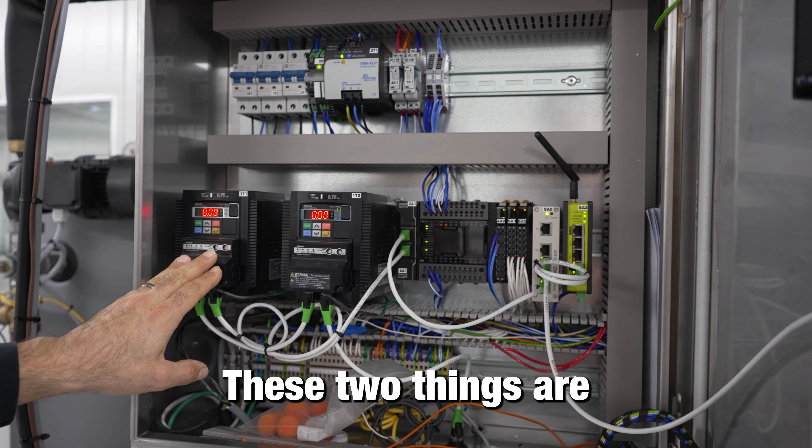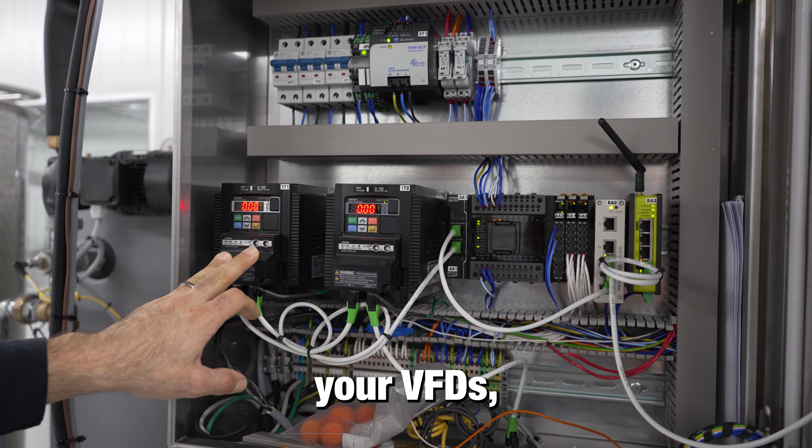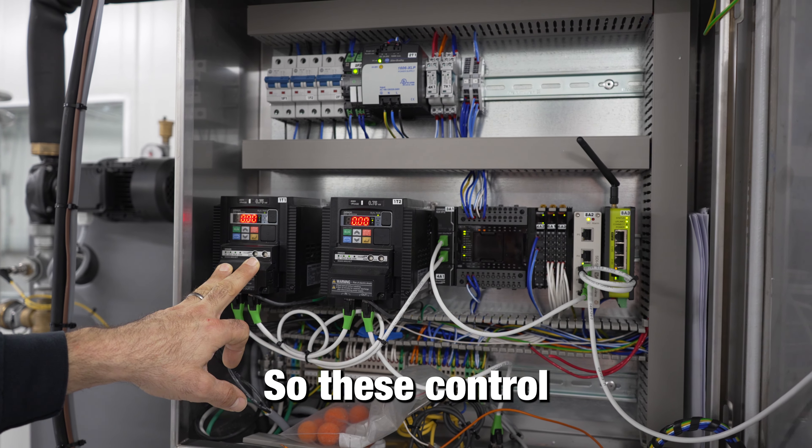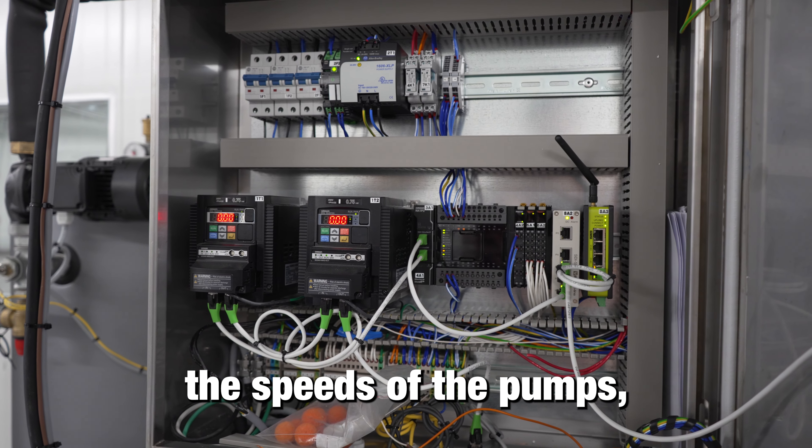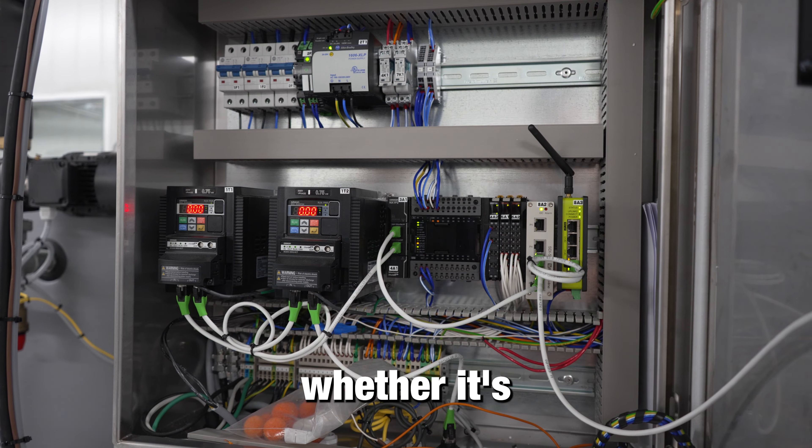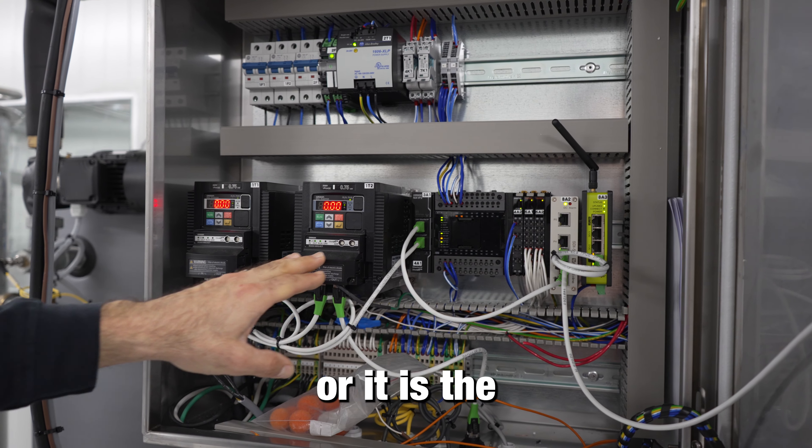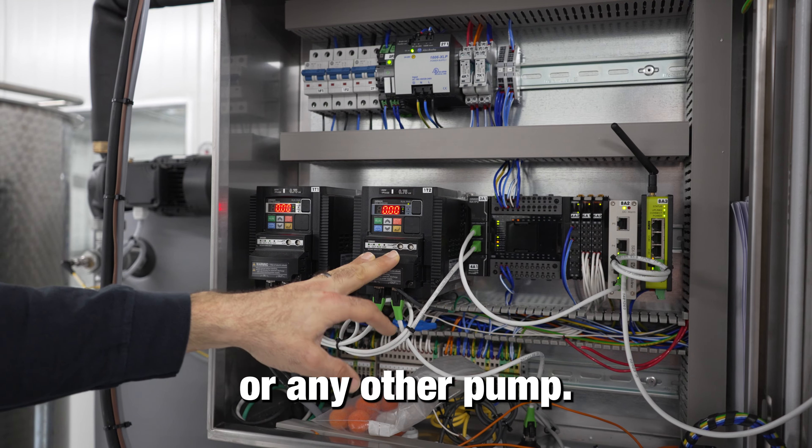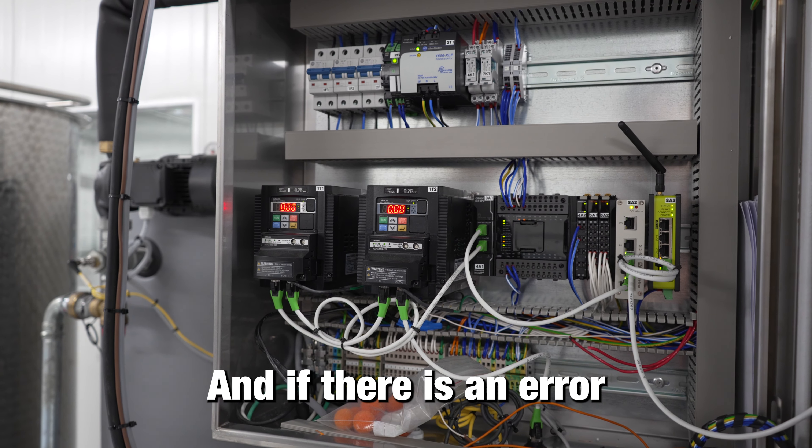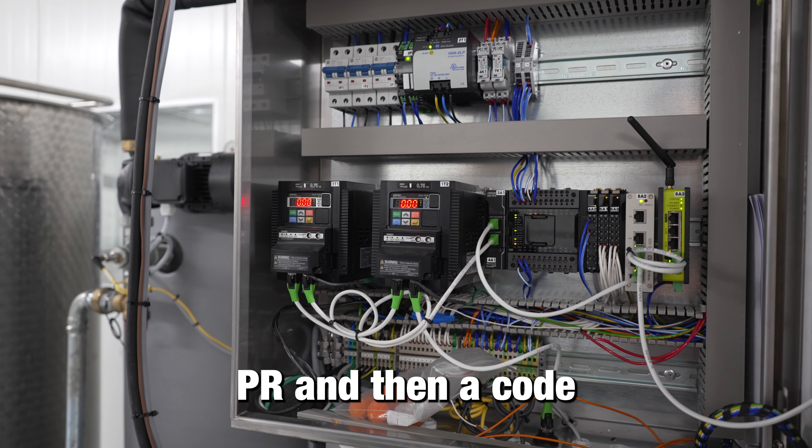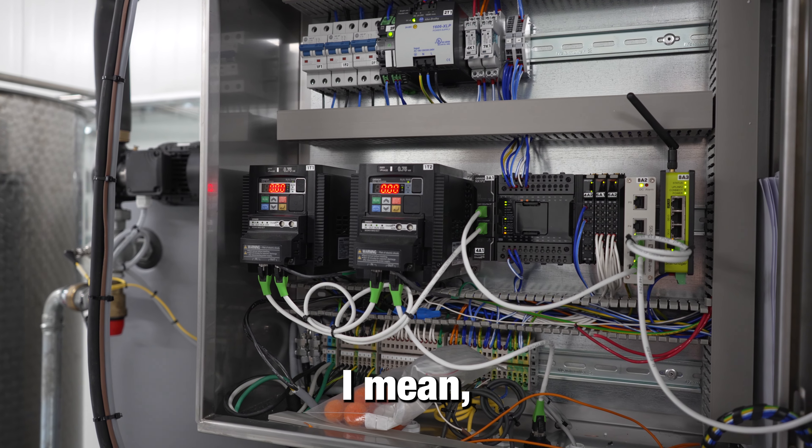These two things are your VFDs, variable frequency drives, so these control the speeds of the pumps, whether it's the product pump or the hot water pump or any other pump. If there is an error on these you will see it says ER and then a code.